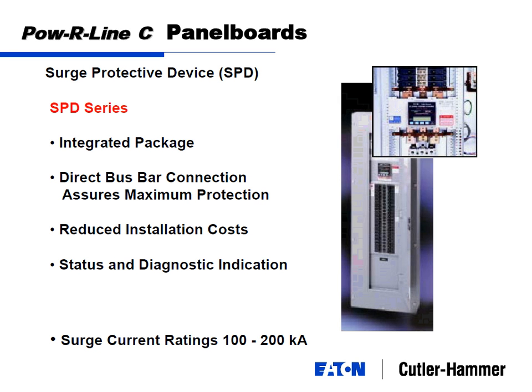And the largest lightning strike ever recorded is 200,000 amps. I don't think you'll get that necessarily unless you're standing on the roof, but I'm sure there's been larger, but never recorded. But when you start to get into the building, that's kind of the range you're looking at. And this thing will be built to handle whatever it's rated for. And in panel boards, you can go up to 200K, and you can go up to 500 or 600 even in larger switchboards. But all that the rating means, they call them surge current ratings, all that means is how much can I withstand.